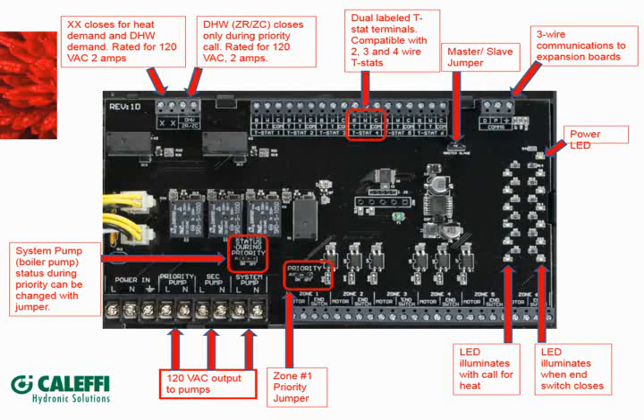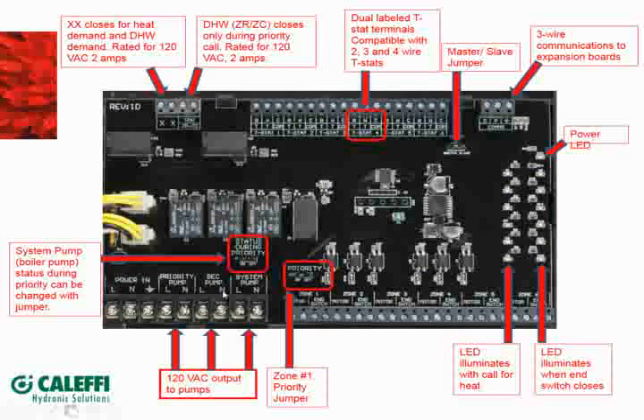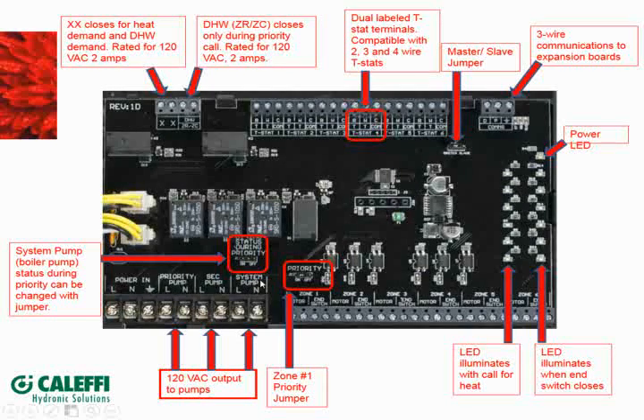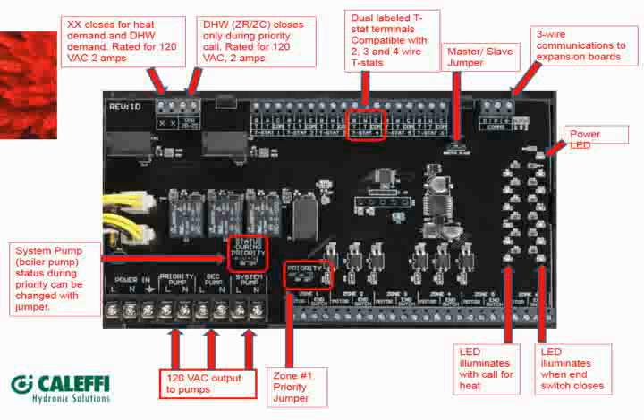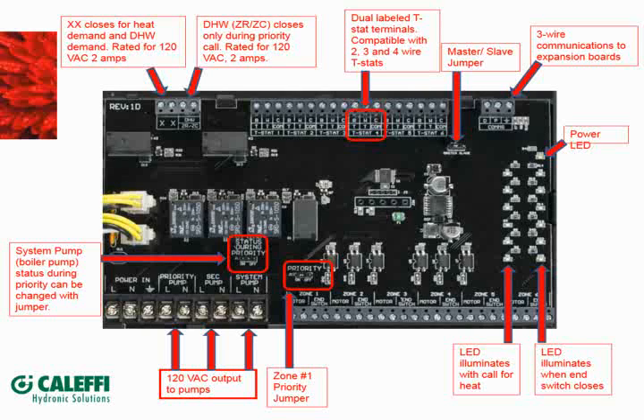Some other manufacturers, zone 3 might be priority, and then if you get a 6-zone, zone 6 might be their priority. And then we have 120-volt outputs going to the pumps. So we have a priority pump, a secondary pump, and what we call a system pump. The reason we call it a system pump is that it could be a primary pump on a primary-secondary system with, let's say, a Modcon boiler and a hydro separator. But at the same time, if it's a cast iron boiler, there might only be one pump in the system, so then you would connect that to this system pump. And this doesn't need jumpers. Those are powered right out of the box. Right, line and neutral to each one of them.